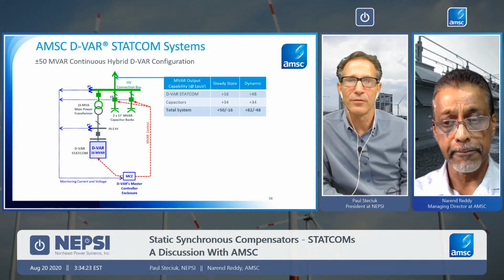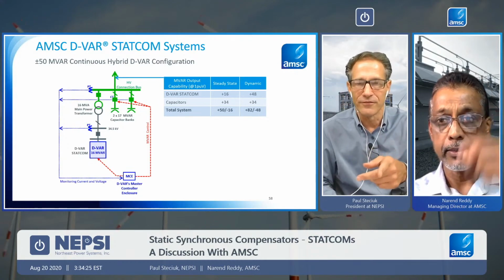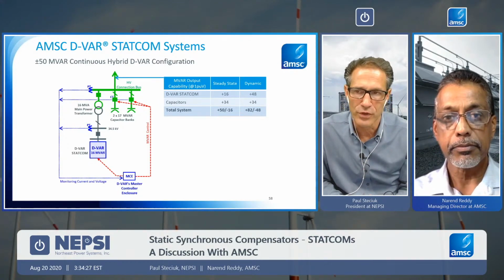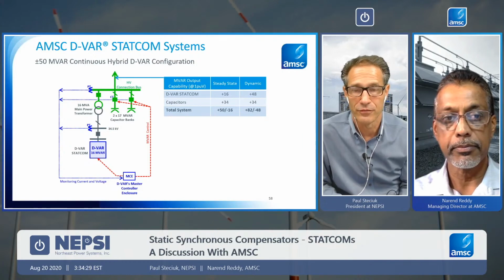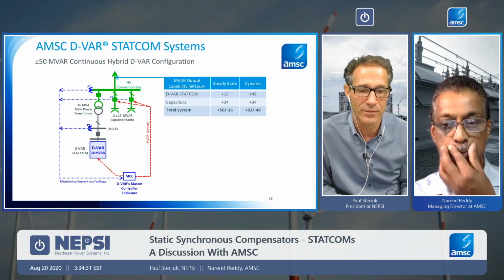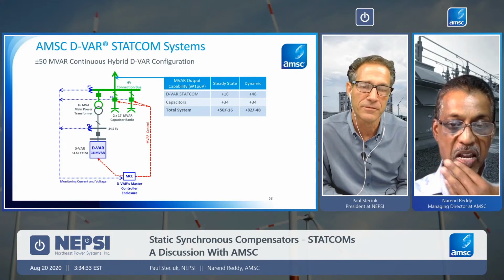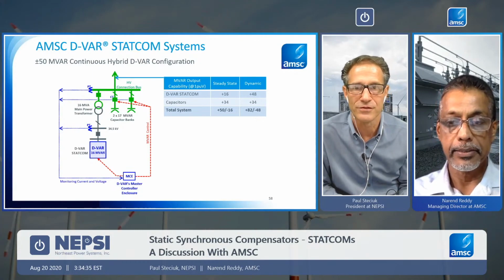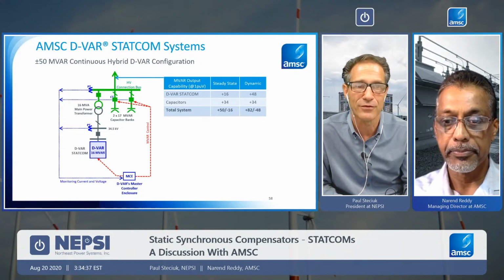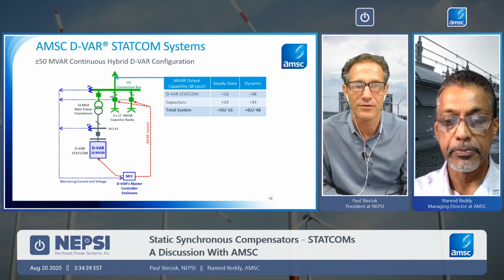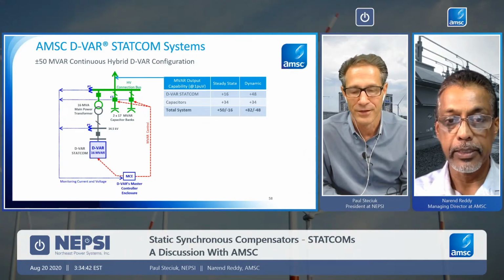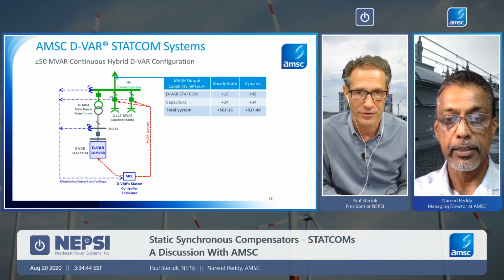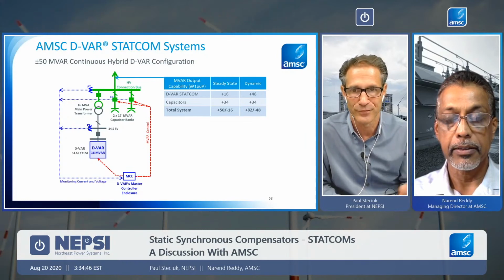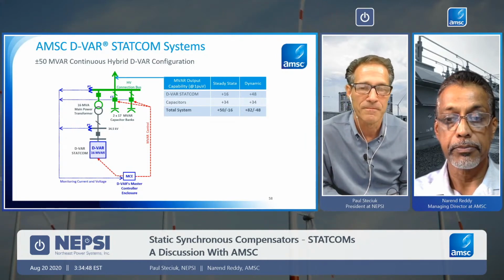Yeah. So I'll bring up a couple points for fast discharge. We have supplied many systems where we can fast discharge a capacitor bank. Typically, you have to wait 5 minutes, but we have installed fast discharge systems that make those capacitors available within a couple of seconds. And so this is something that would interest you in this area where you're doing hybrid systems.